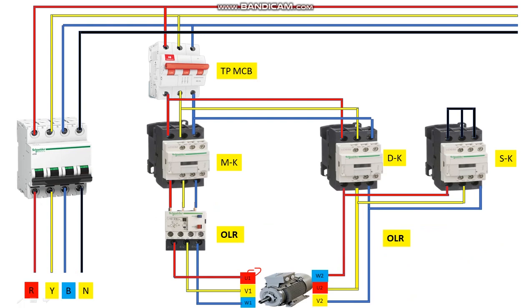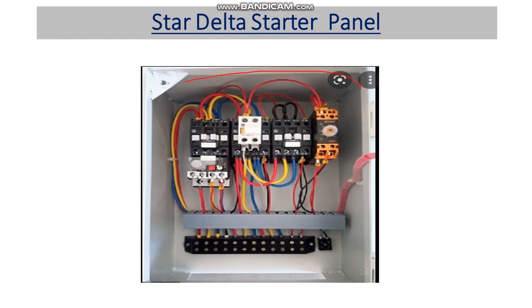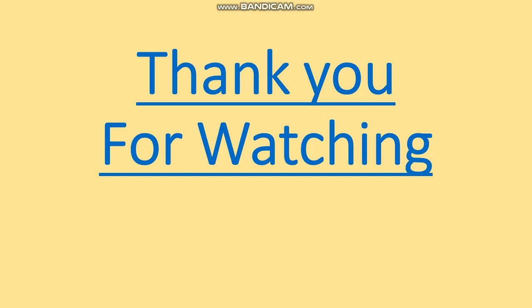That's how we do the power wiring of a star delta starter. This is the internal view of the star delta panel showing the main contactor, delta contactor, star contactor, and on-delay timer. Two-pair cables go from the main contactor side and the delta/star side to the motor terminals. We'll discuss the control wiring in the next video. Thank you for watching — please like, share, comment, subscribe, and hit the bell icon.